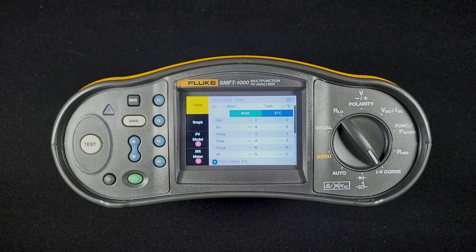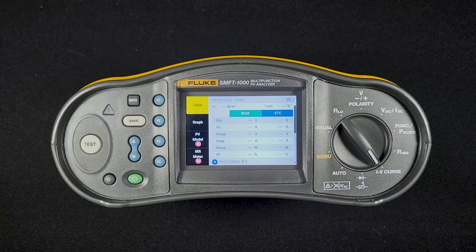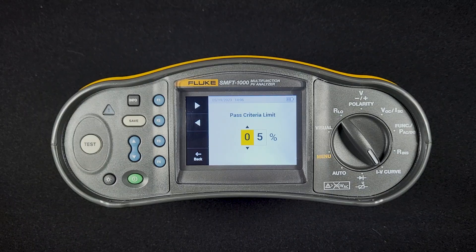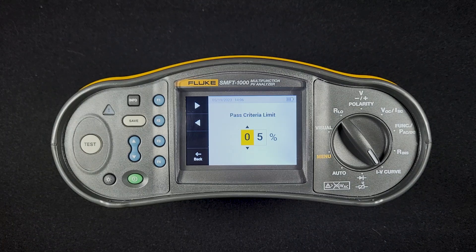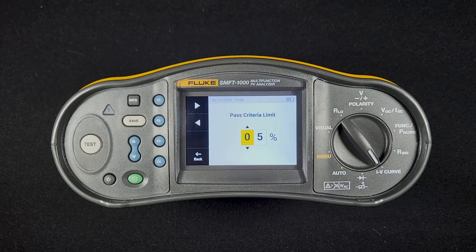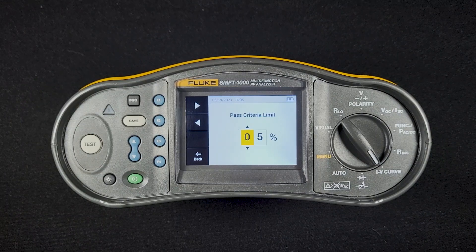STC is our measured value converted to what the module would be doing under standard test conditions. In this screen, we can also push the down arrow and set our passing criteria limit. It defaults to 5%, which is the IEC 62446-1 standard for IV curve tracing modules. If you change this up or down, that's going to impact whether a result is a passing or failing result. You'll still get the actual numbers, but this is what affects the red Xs and green checks.